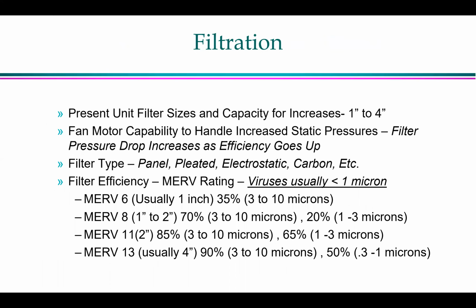So next. So filtration. We've got the outside air coming in as we can, but the present filtration can be 1 to 4 inches. But with changing the filter, the better filter you get, the higher the pressure drop. So you have to be careful that whatever you change the filter to, the air handlers will handle. A university recently sent a directive out to change every filter in the university to MERV 13 or 14. A lot of them could only handle 1-inch filters, so they had a really high pressure drop, and all of the direct expansion systems in the university froze up. So they couldn't do it. So be careful of what you try to ask for.